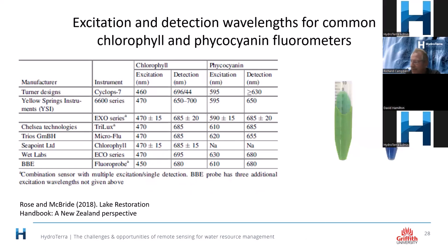Specific wavelengths for excitation and specific wavelengths for detection: the green for chlorophyll, the blue for phycocyanin. Typically you're looking at an excitation wavelength of about 470 nanometers of blue light and a detection wavelength of around 670 nanometers for chlorophyll. Phycocyanin, you're looking at exciting it at about 600 to 610 nanometers, with a detection wavelength pretty close to the chlorophyll detection. So you can see some of the challenges.